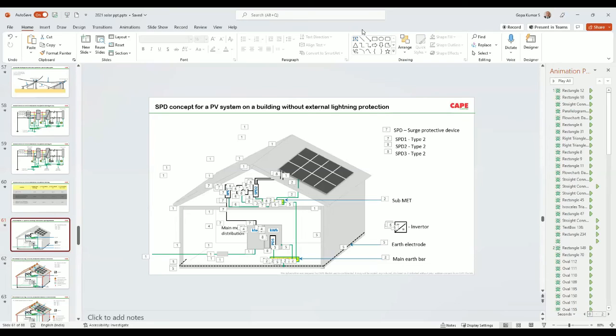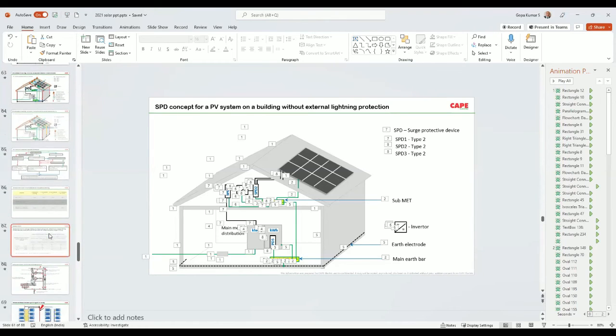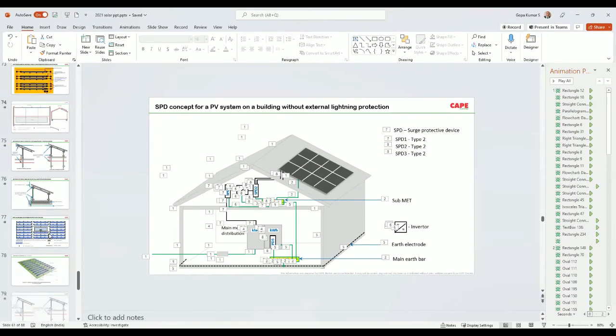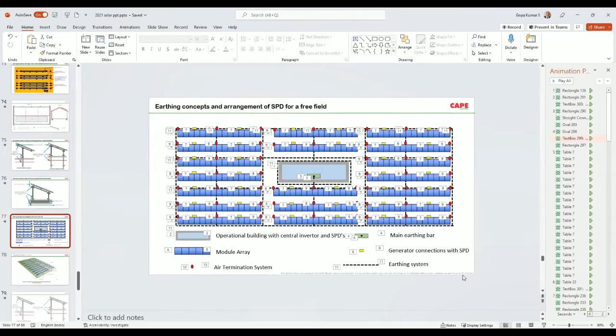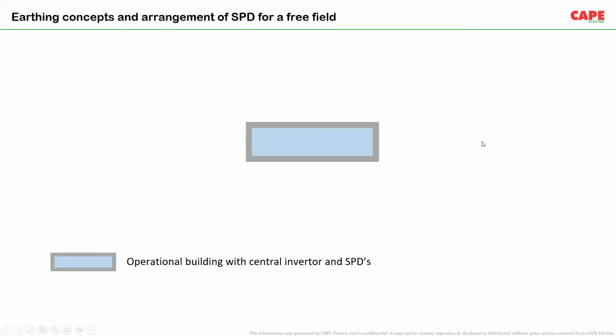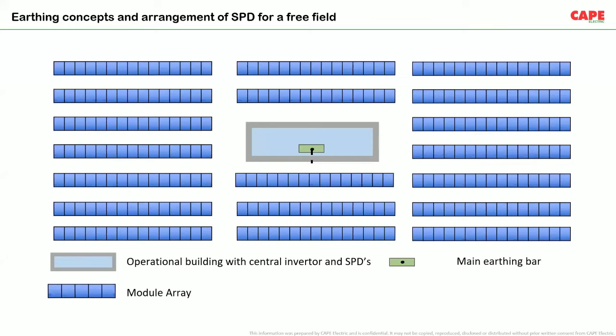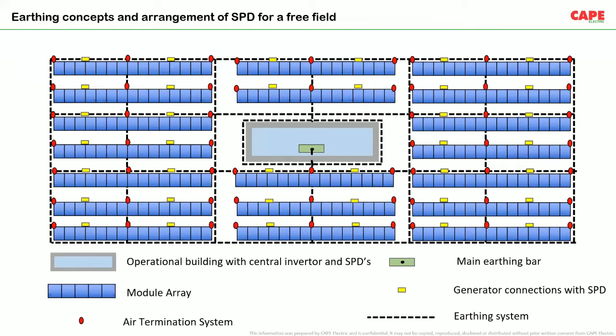One information which I wanted to share with you is the earthing of a large PV installation. You can see here, a ground mounted system. So here you have the control room, you have the main earthing bus bar, and finally the earthing is made as a grid interconnecting every frame of the solar PV. The grid size can be based on the recommendation from the standard.